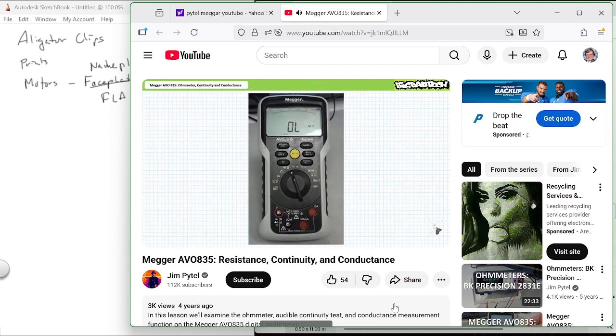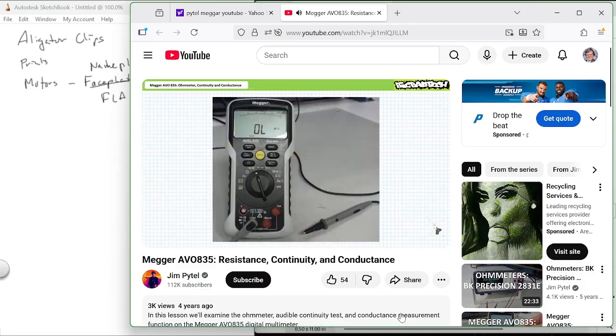To place the Megger AVO 835 into ohm meter mode, rotate the function dial to the selection with the ohm symbol. We'll explore other functions and the function buttons in later lectures. In this position, the AVO 835 allows access to the black common terminal and the red live terminal on the left, identified with an ohm symbol. Black lead into the black hole. Red lead into the red hole. An ohm meter measures the resistance of an element in units of ohms placed between the two tips of the leads. The element under test must be depowered and isolated from the system.